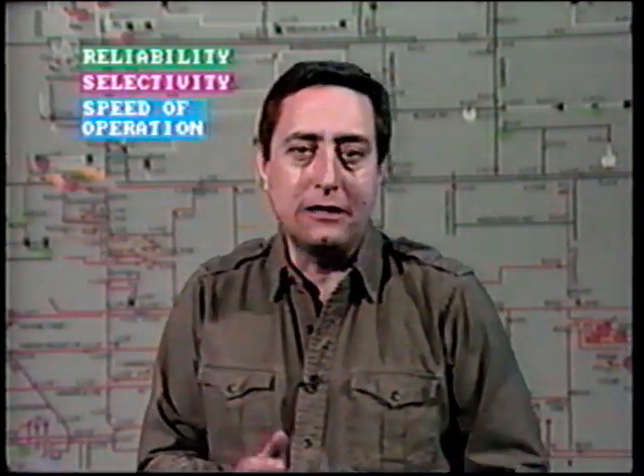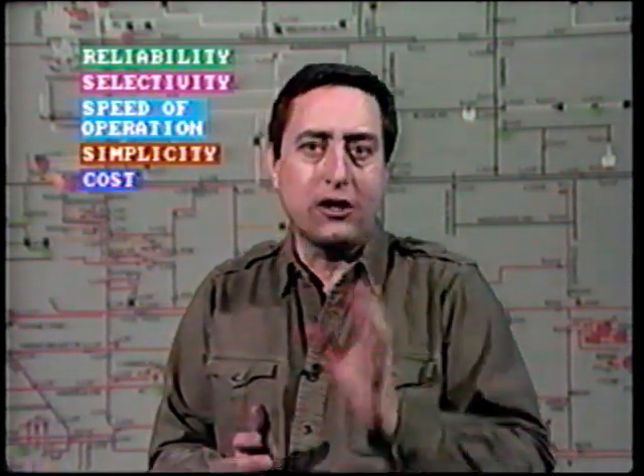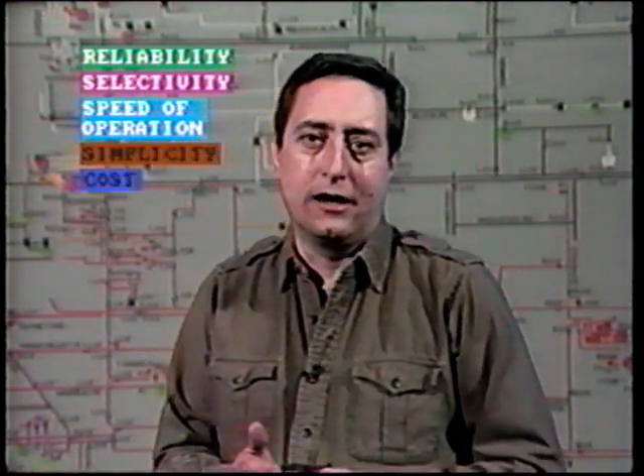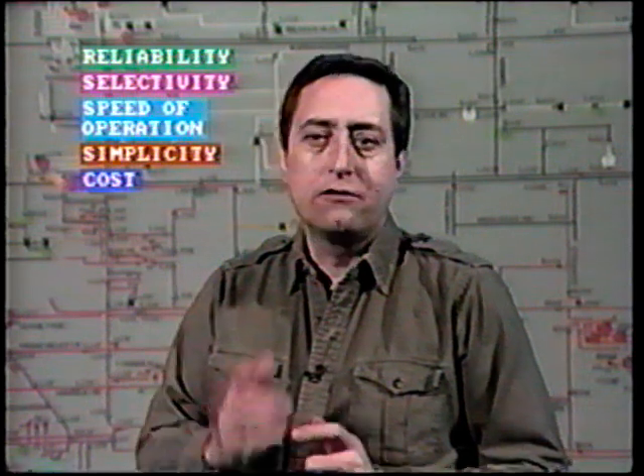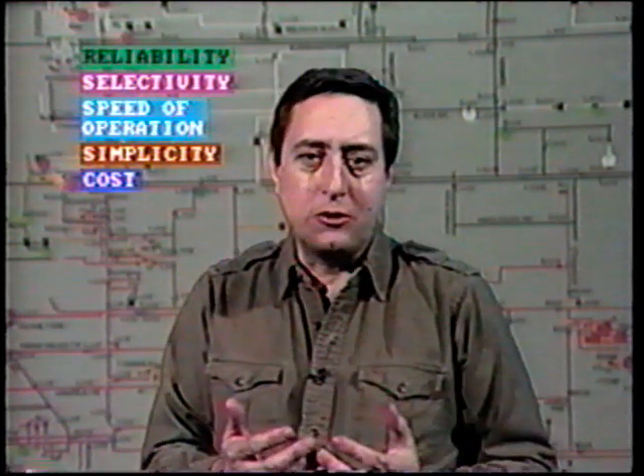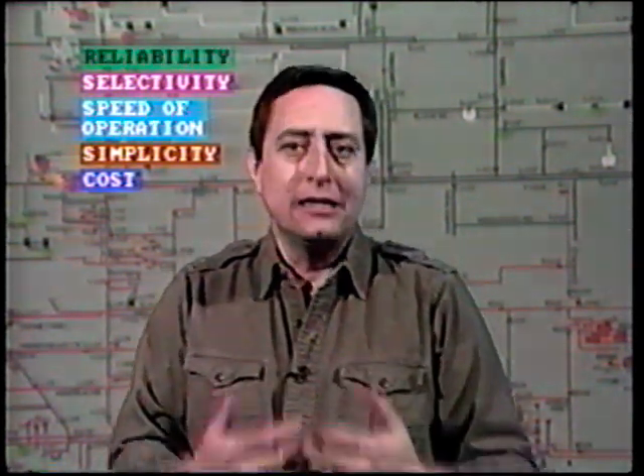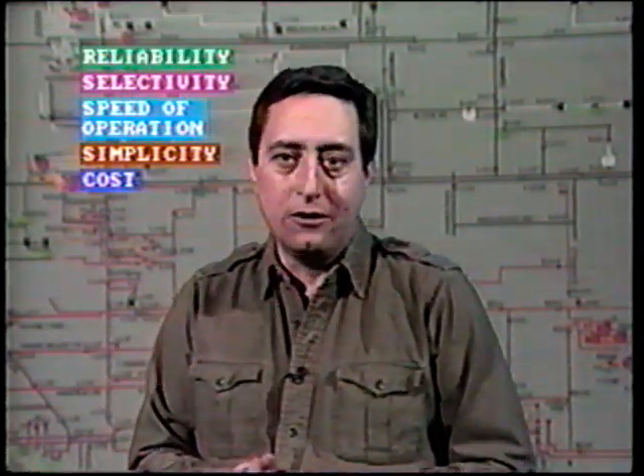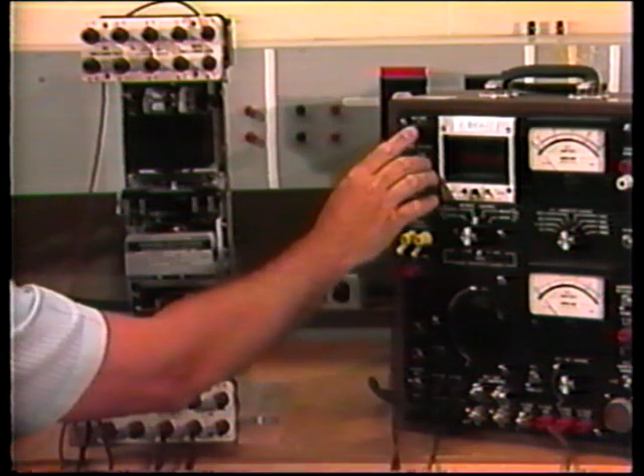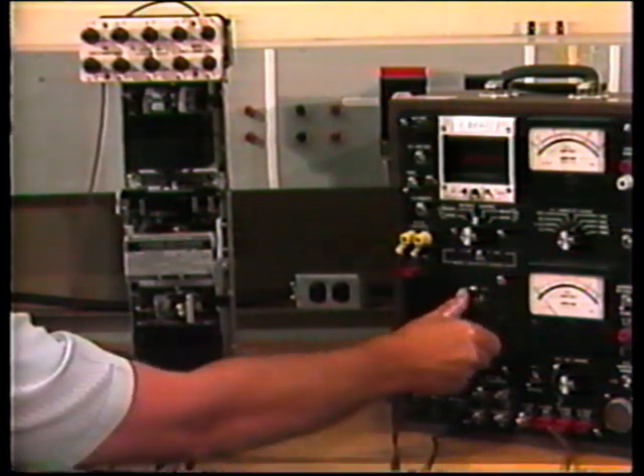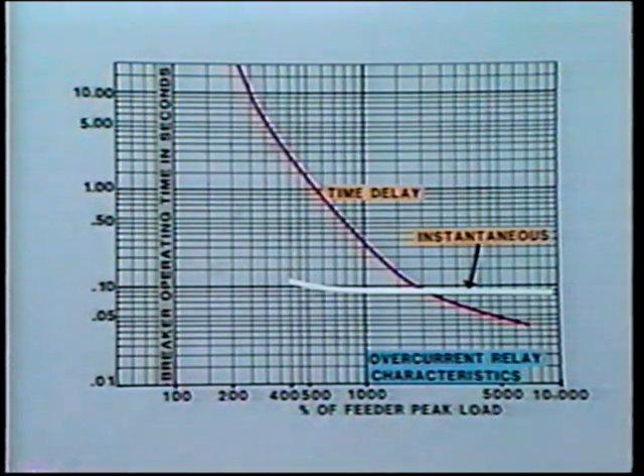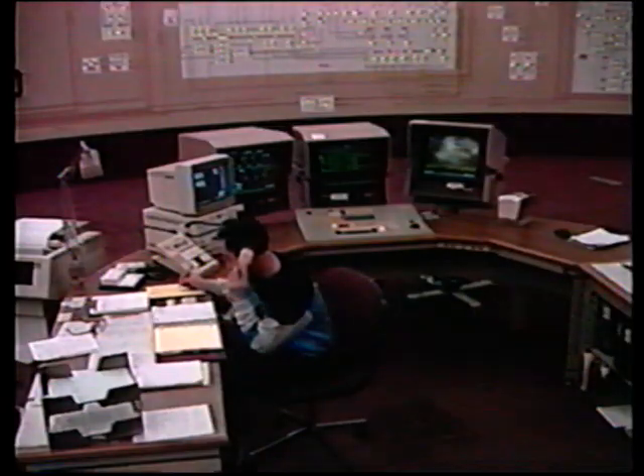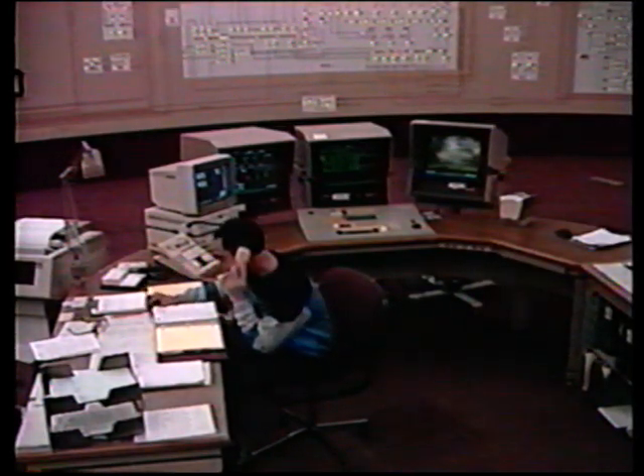To summarize now, we can say that there are 5 basic factors in application of protective relays. And these are 1, reliability, 2, selectivity, 3, speed of operation, 4, simplicity, and 5, cost. The last two items speak for themselves, but let's look a little closer at the others. First, we have to rely upon the relay or relay system operating correctly. That is, to operate and trip out the faulty circuit when it's necessary to do so. The reliability of the relay is tested by inputting current and voltage which simulate fault conditions. The time of operation can be measured in relation to the degree of fault condition. A second aspect of reliability is that the system must not trip out during normal operation.